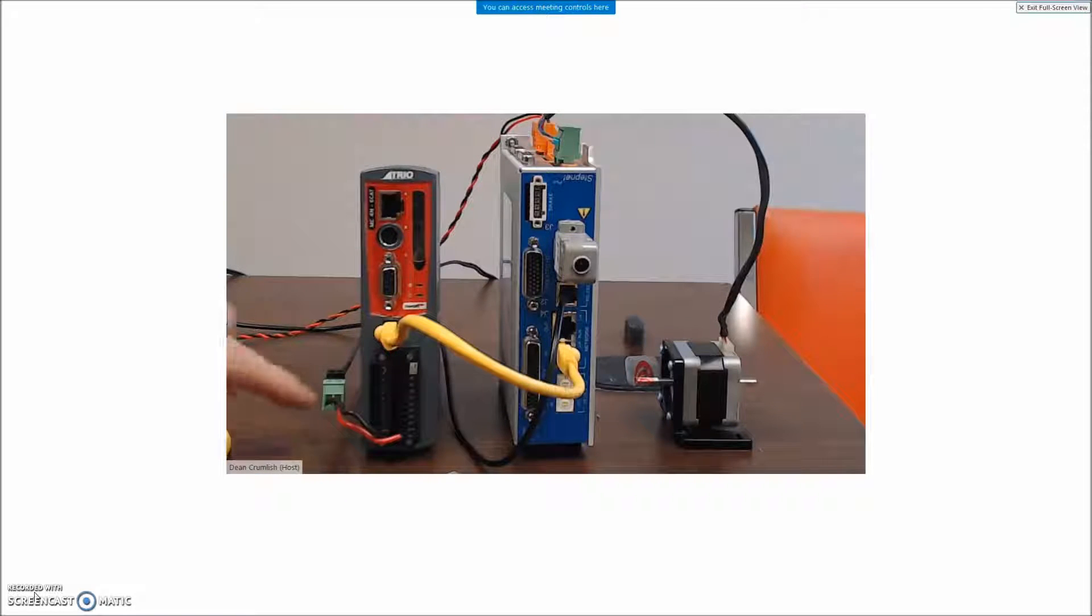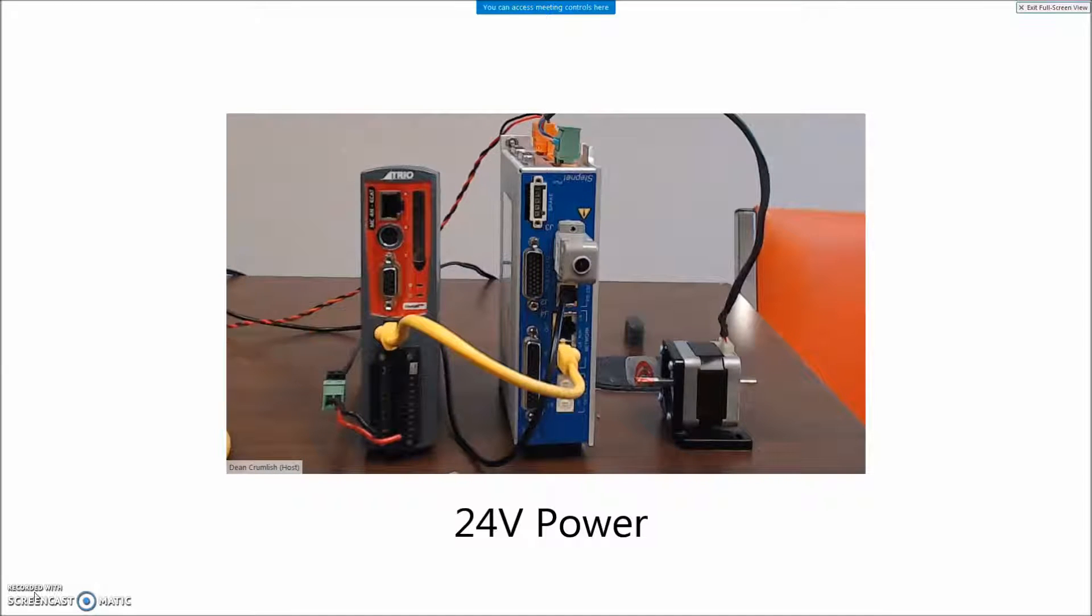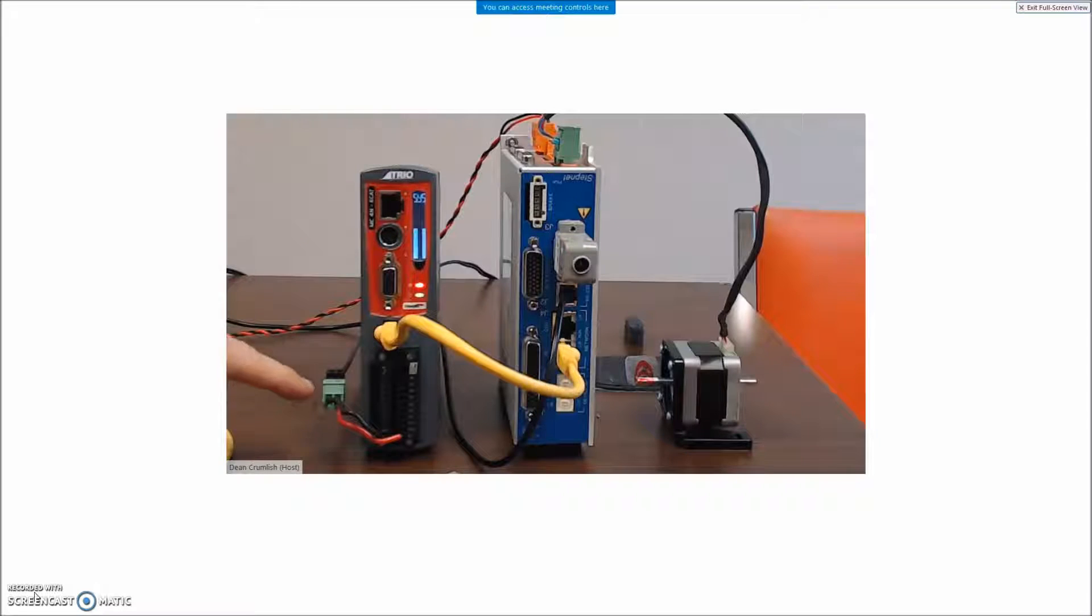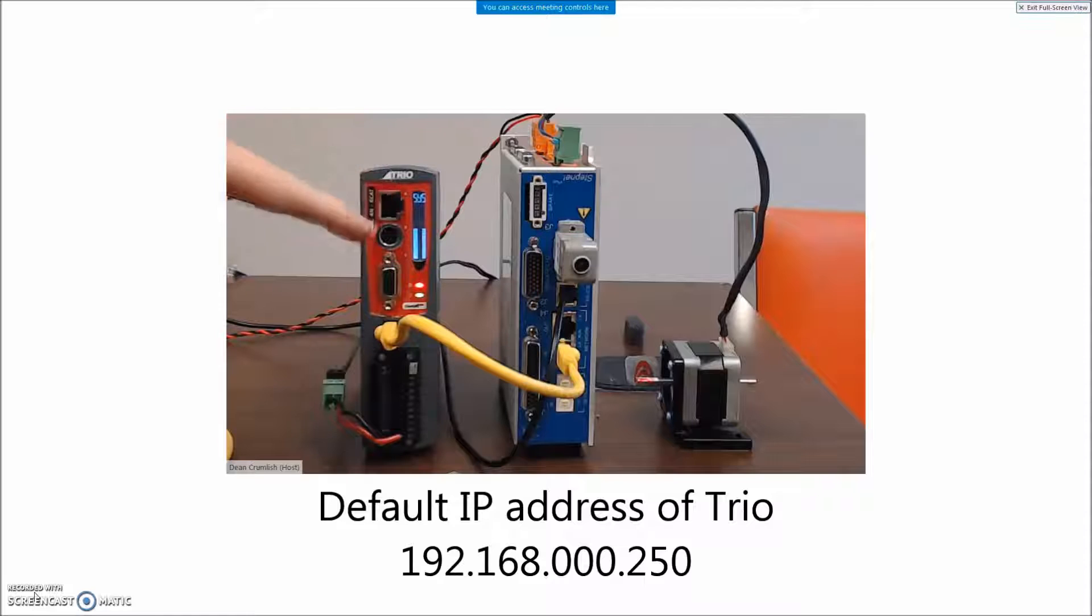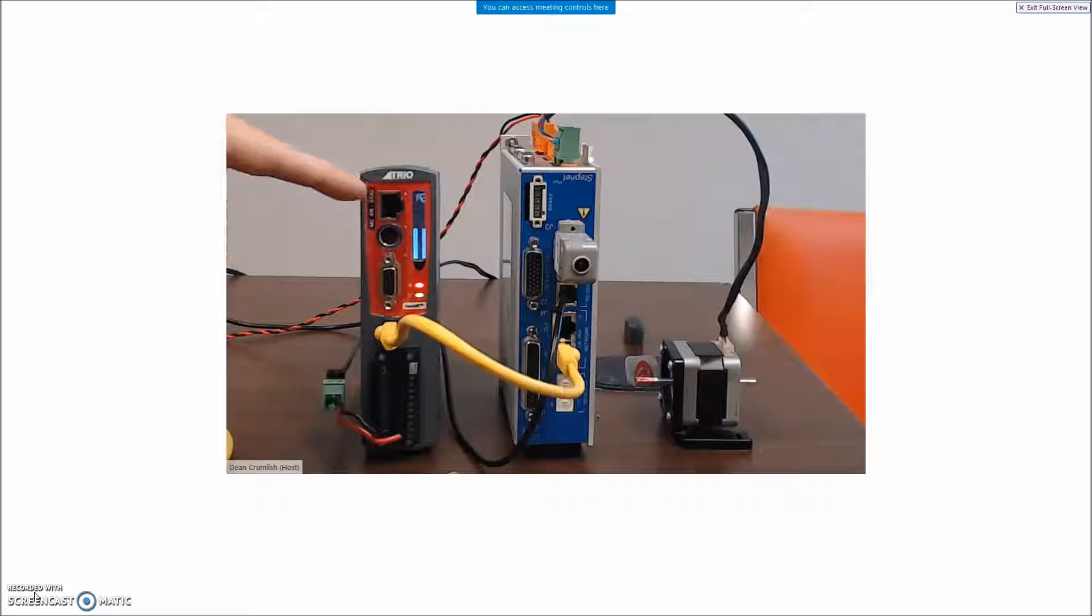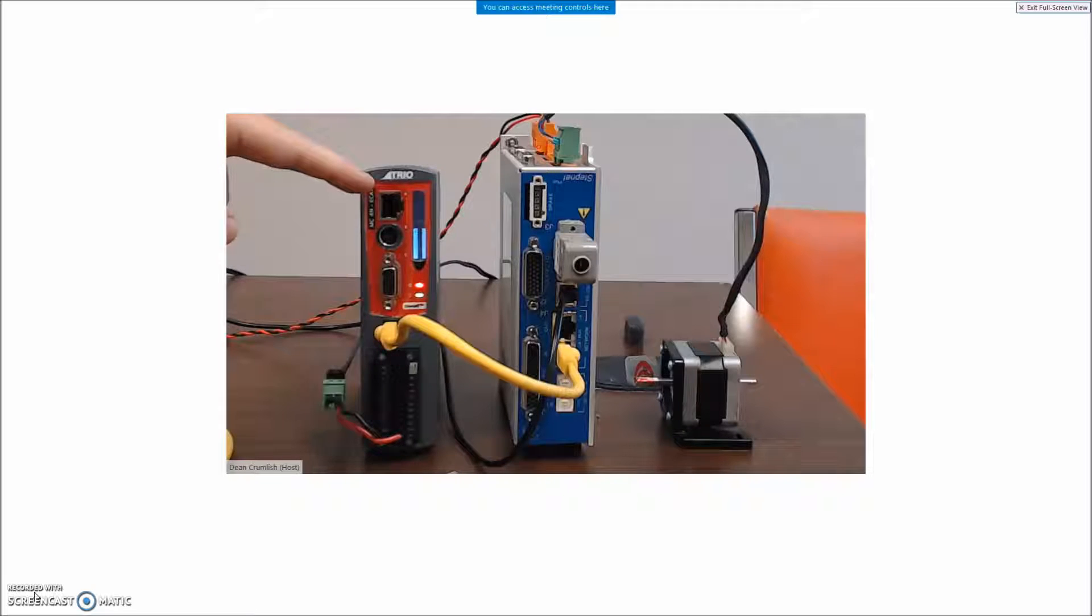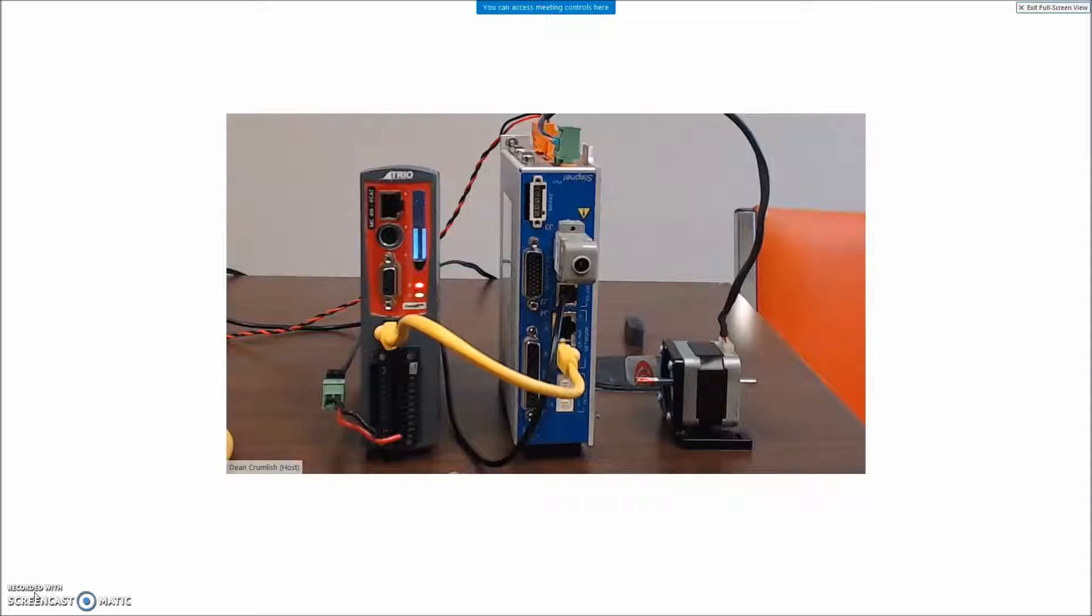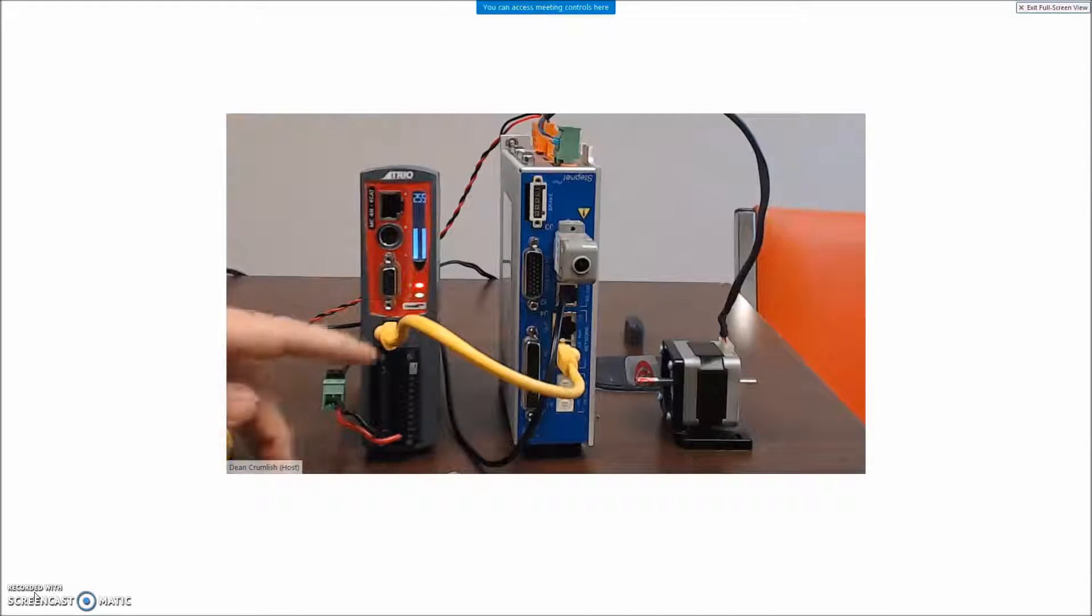We have 24 volts on the connector and when we turn the power on to the 24 volts we'll see a system display here with the IP address of the device. So IP 192.168.0.250 and then a subnet address 255.255.255.0. We can configure the PC with that but we do need to know the IP address of this device.